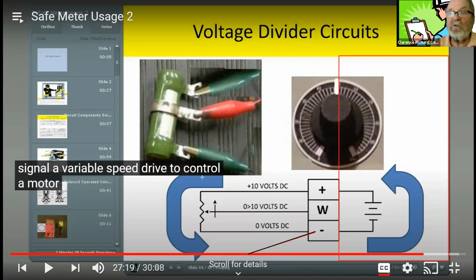That's what's bad. Yes, we were looking at 10. That was the reading we were looking for. But the thing that was bad was the fact that we didn't have the 10 volts. Therefore, we had a broken wire. We had 0 here, 10 volts there. That's the entire pressure drop of the power supply across it. It tells you you have a broken wire.